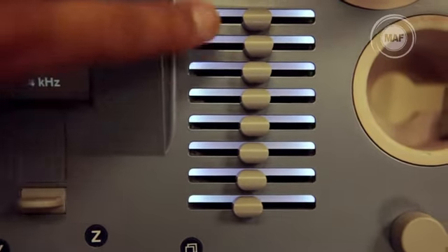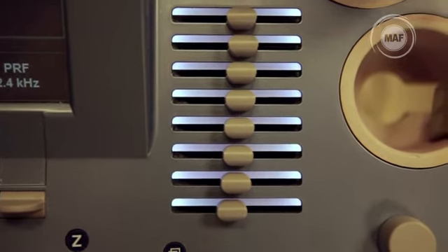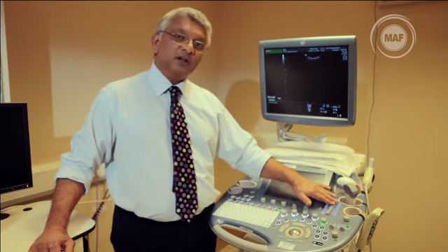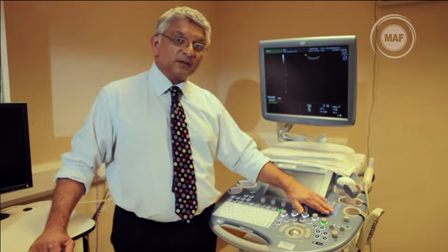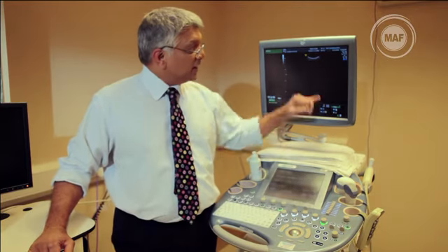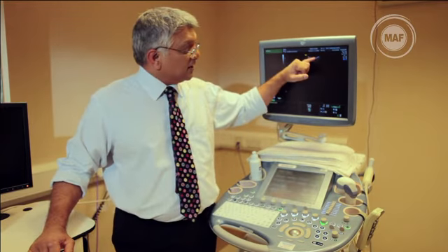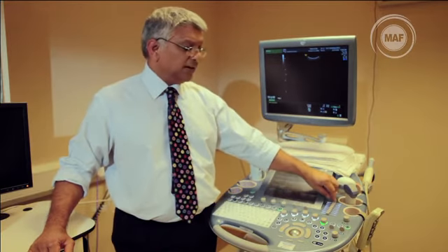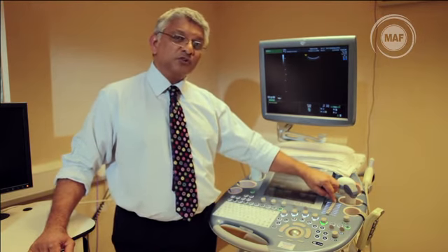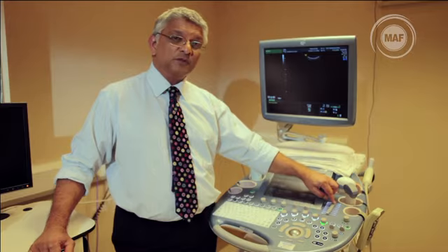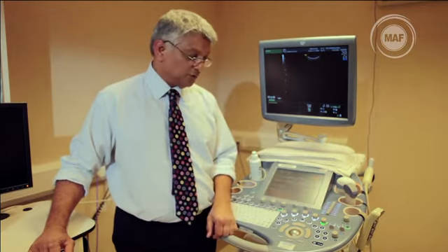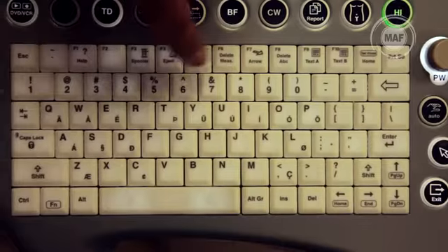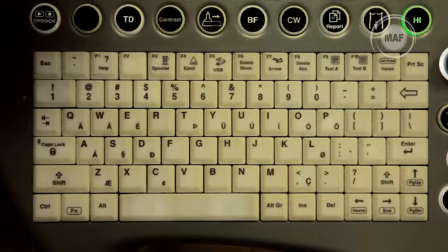You'll see some sliders. That's called the TGC, time gain compensation. Usually they're in the middle, which is the default setting. And what does a slider do? It adjusts sections of the screen. So the first slider may adjust the 0 to 2 centimeters, the other one 0 to 4, and so on and so forth.